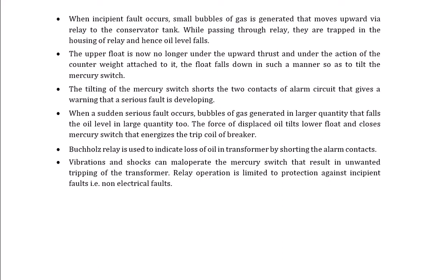Okay, so when a sudden serious fault occurs, bubbles of gas are generated in a large quantity, which drops the oil level by a large amount too. The force of the displaced oil tilts the lower float and closes the mercury switch that energizes the trip coil of the breaker.